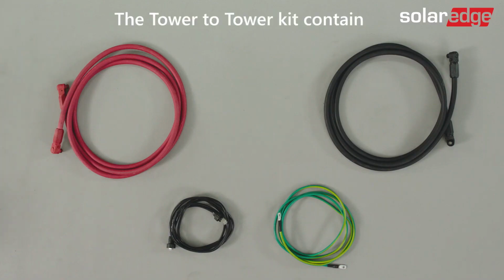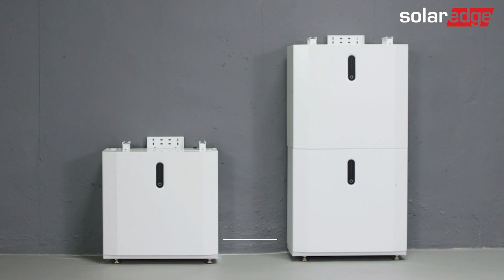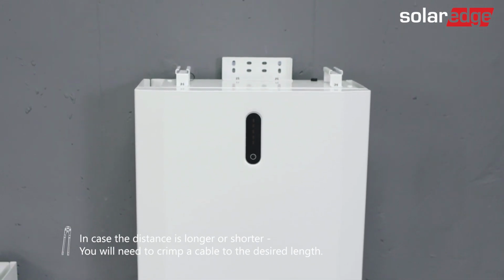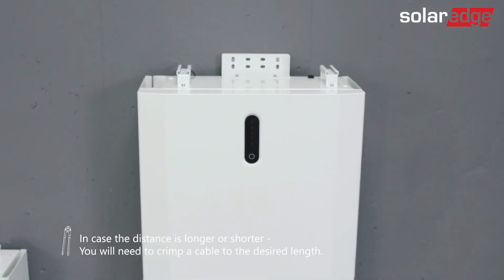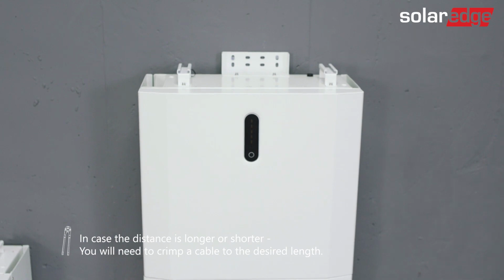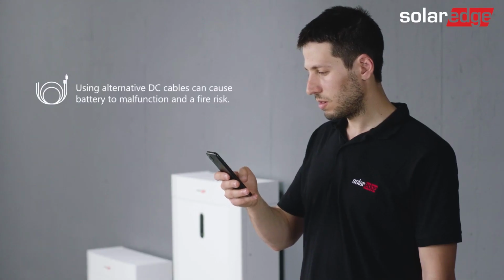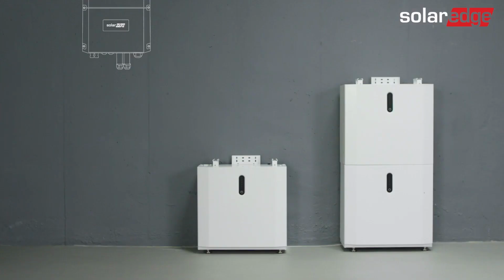The tower-to-tower kit contains 2 DC cables, a communication cable, and a grounding cable. Please notice that the cable length fits a 30 to 40 centimeter distance from tower to tower. In case the distance is longer or shorter, you will need to crimp a new cable to the desired length. Please refer to the SolarEdge user manual for supported cables and pin assignment. Now, connect the cables between the bottom batteries in each tower.